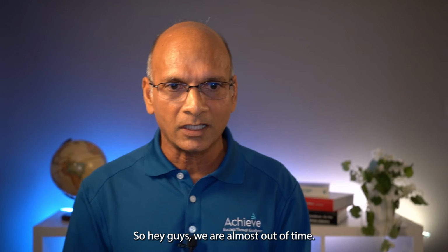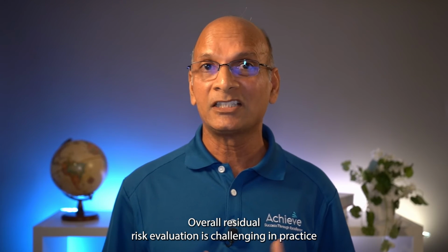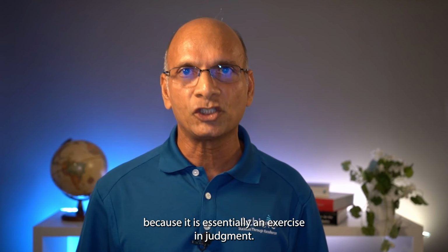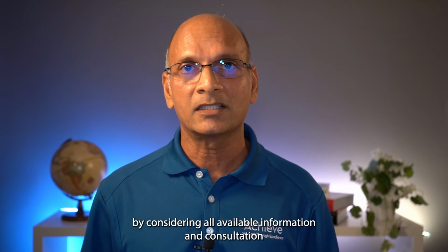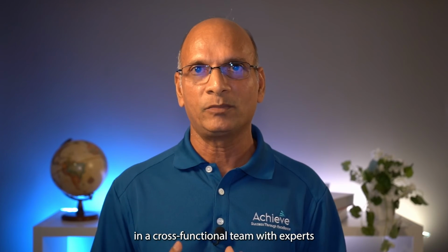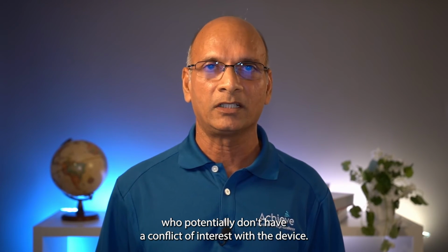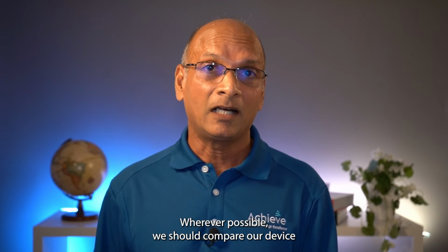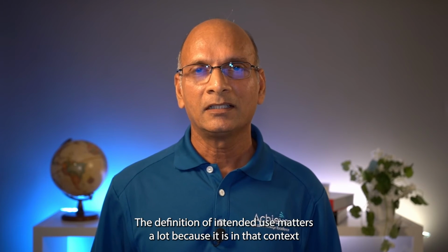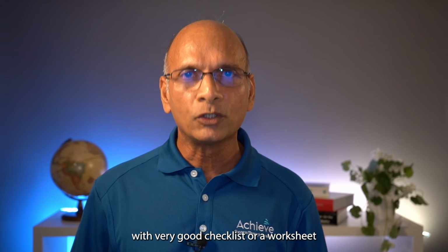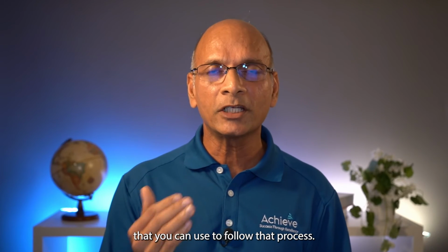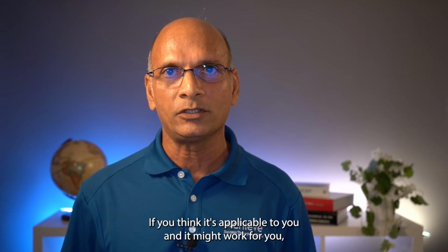So hey guys, we are almost out of time. So let me very quickly summarize what we talked about today. Overall, residual risk evaluation is challenging in practice because it is essentially an exercise in judgment. However, that judgment should be made by considering all available information and consultation in a cross-functional team with experts who potentially don't have a conflict of interest with the device. Wherever possible, we should compare our device with a predicate device or any other similar device. The definition of intended use matters a lot because it is in that context that we are evaluating our overall residual risk. And FDA has provided some guidance documents with a very good checklist or worksheet that you can use to follow that process if you think it's applicable to you and it might work for you.